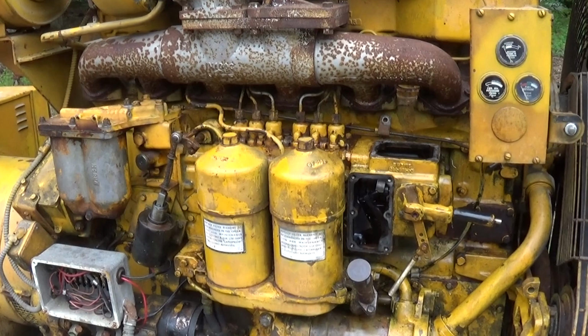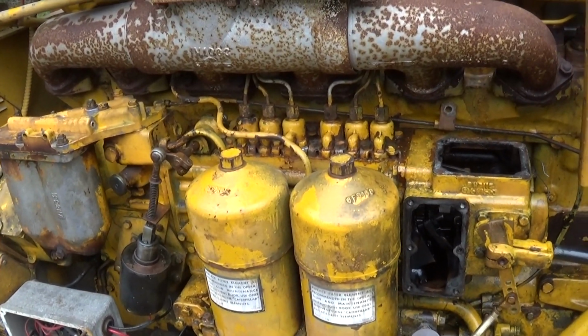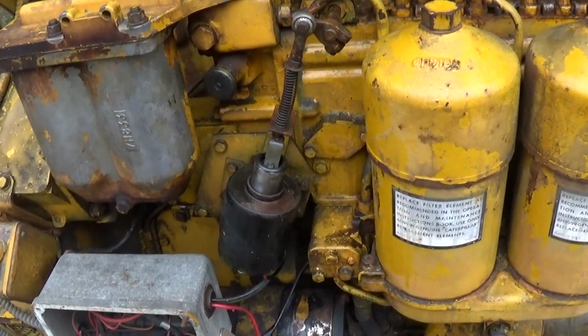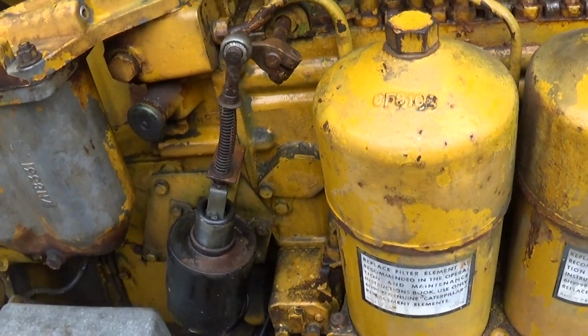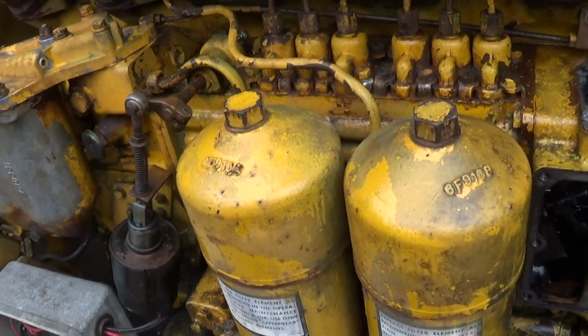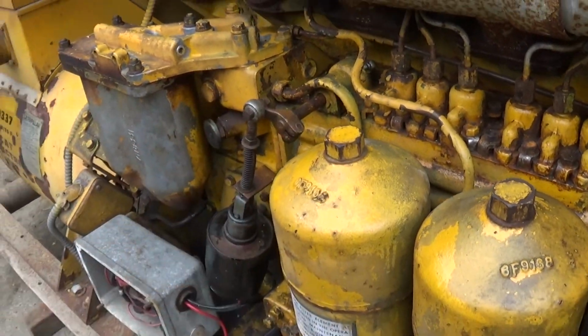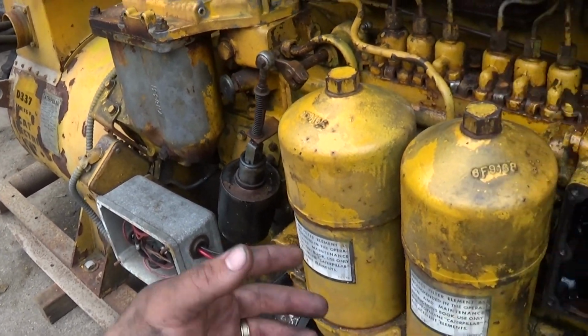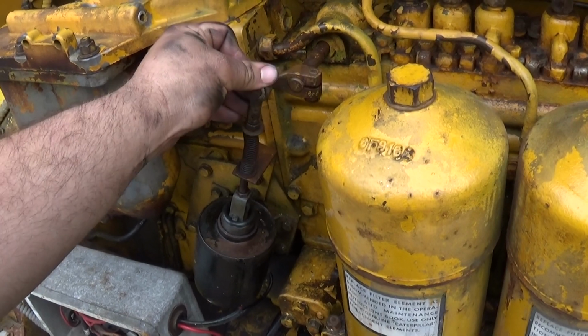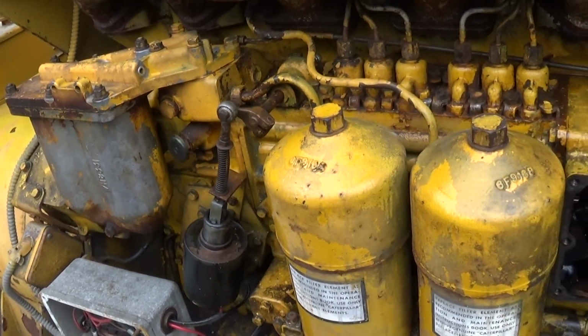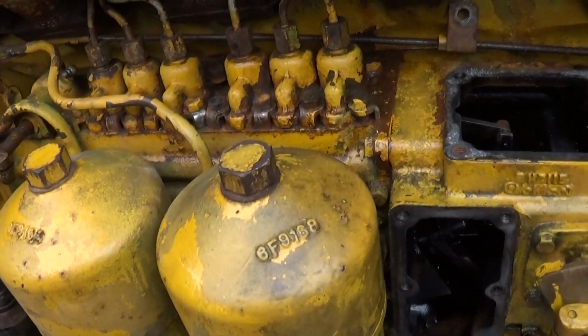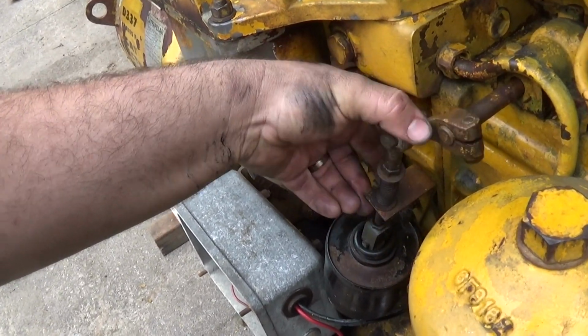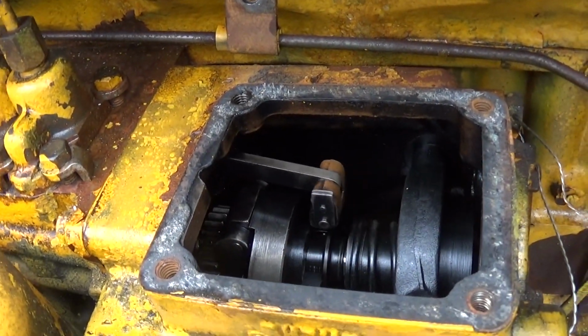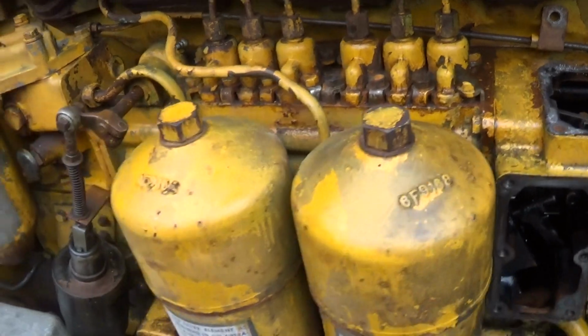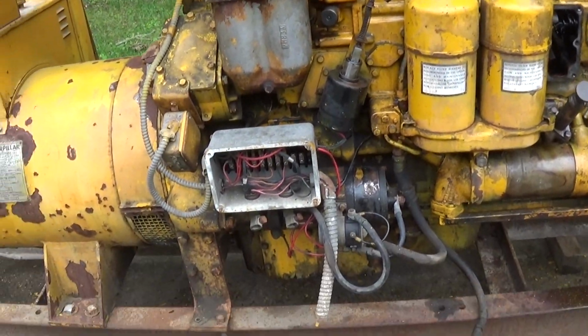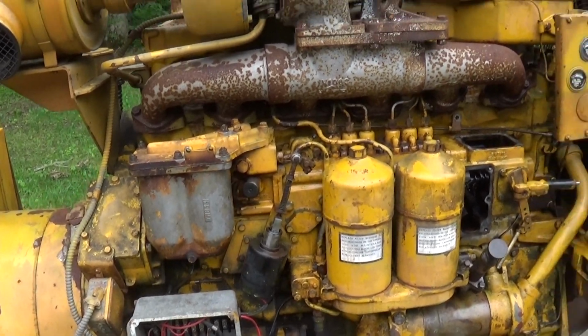Real quick, one thing I forgot, and I'm sure all you Caterpillar guys were yelling at me earlier in the video when I called this the run solenoid, it's not the run solenoid, that's the stop solenoid. This is energized to stop this unit. A lot of old Cats are like that, and I should have listened to my intuition when I started this video. I was thinking that's probably just a shutdown solenoid, energized to stop, like all the old Cats are. Well, for some reason I said run solenoid, but you can clearly see that when this solenoid pulls in, it shoves the rack to the no fuel position. So the only power you need for this thing to crank it up is to turn it over, and if you had a pony engine on it, you wouldn't need any power at all.